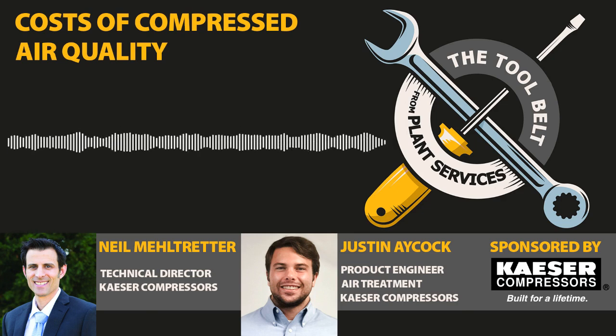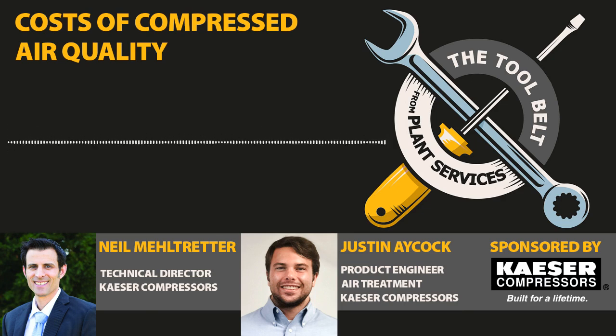Usually you'll have an operator or somebody say, oh, well, that's too low. And then, oh my gosh, you know what? We were running at 125 pounds before, and now we're running at 95. We're saving, for every 2 psi reduction, we're saving 1% energy, and that's pretty huge.